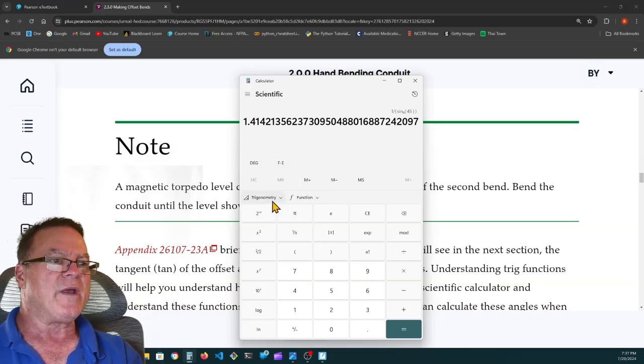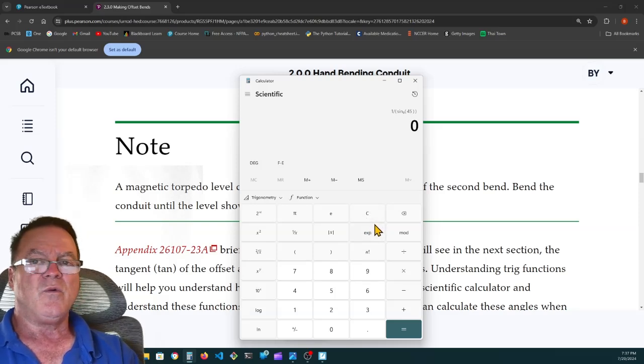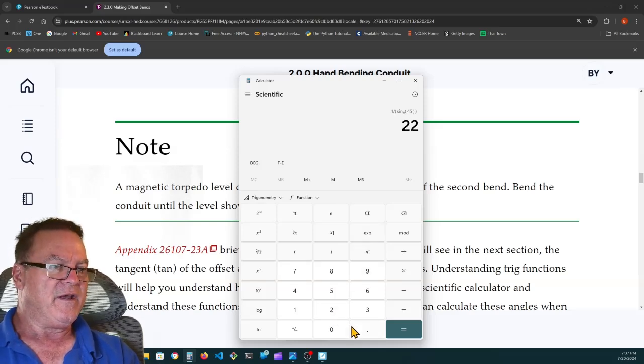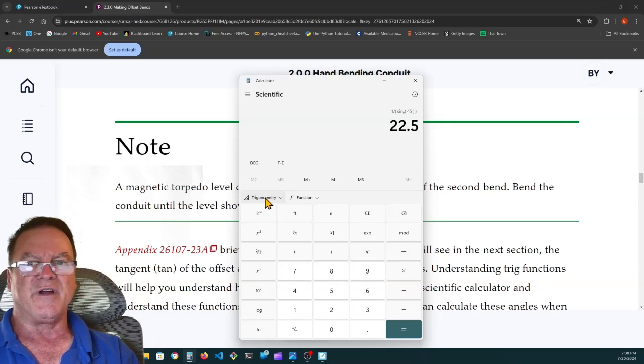And it's nice knowing that because you can figure out other bends. You don't have to memorize them all. Let's say you wanted to make a 22.5-degree bend to make an offset. 30 degrees was too much of an angle. You needed to be shallower to miss another obstruction overhead.